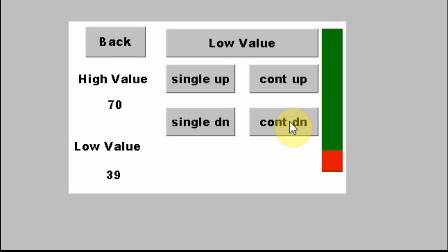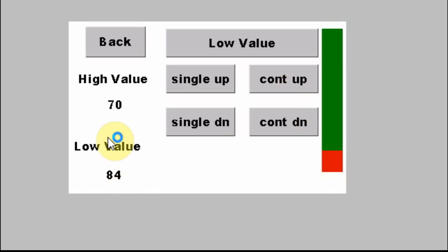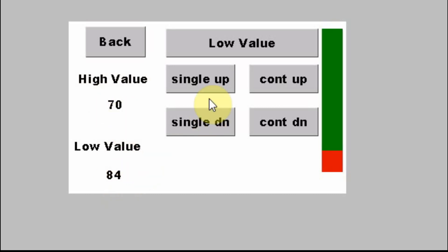I've left a couple of things broken just to show you some things. If I go up and approach 70, the low value should never go above the high value. So when you build your displays or logic, you have to make it check for that. I have it checking for that over here when you single up — you'll see it changes to 69, so it stays below the high value.